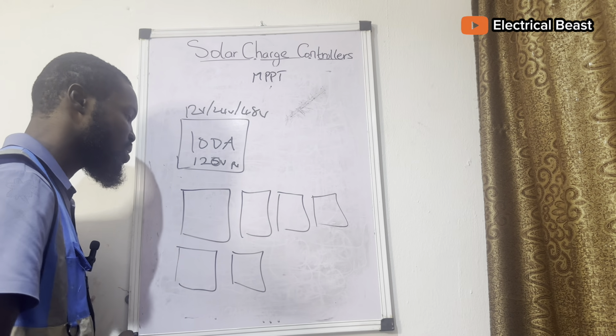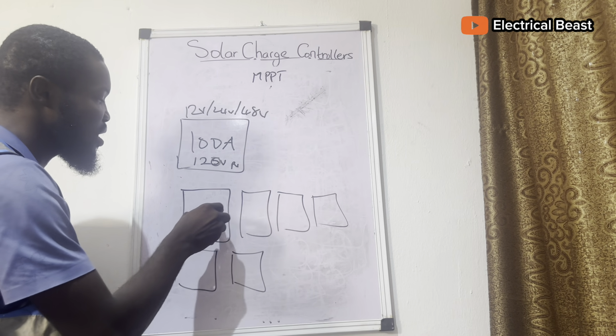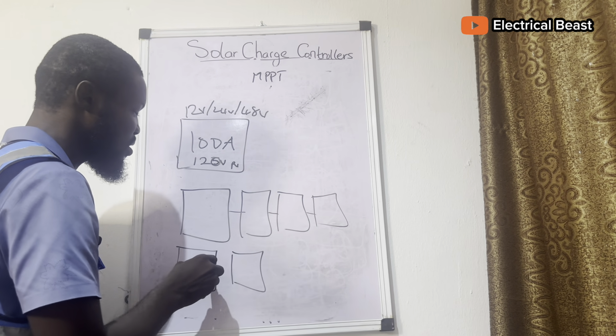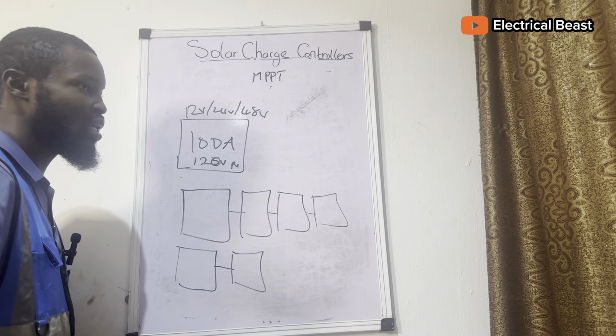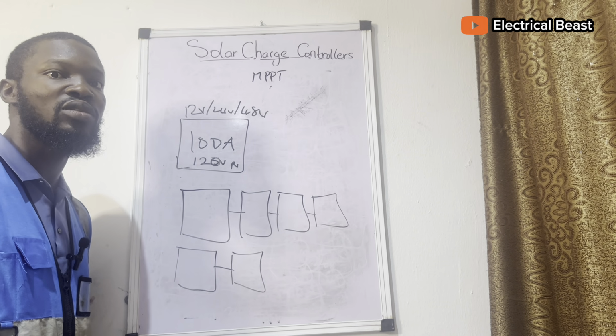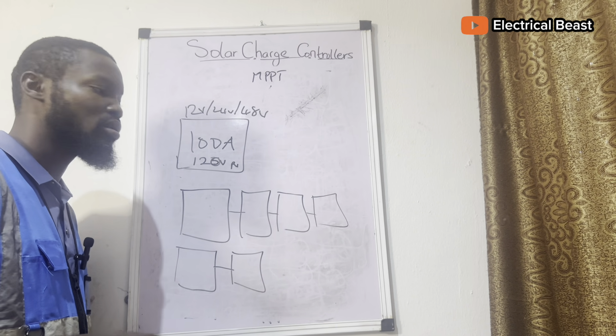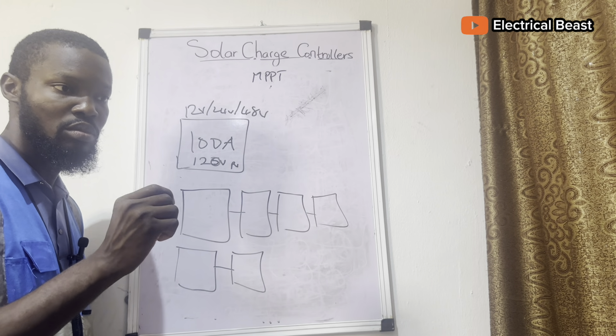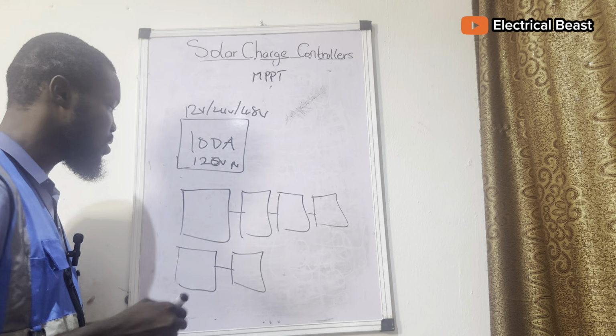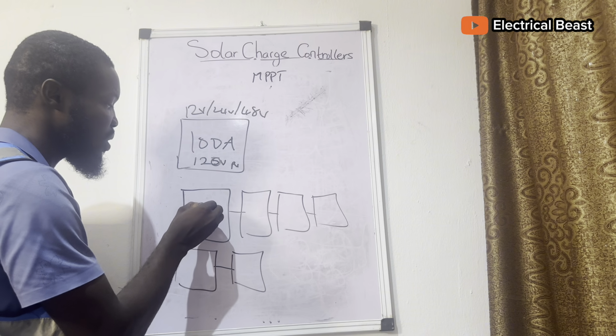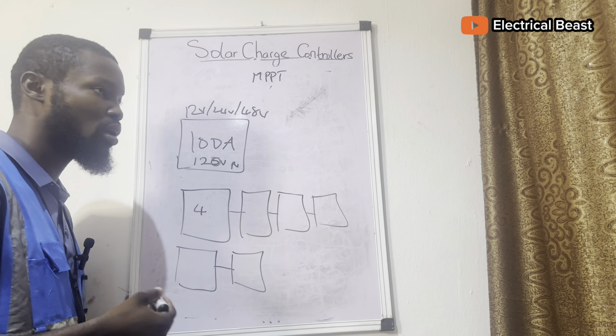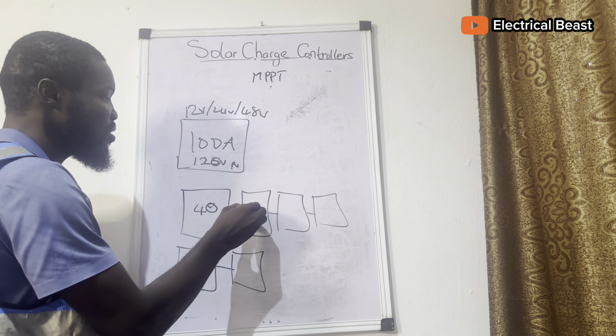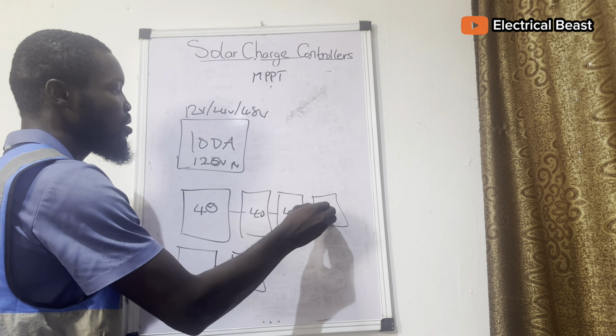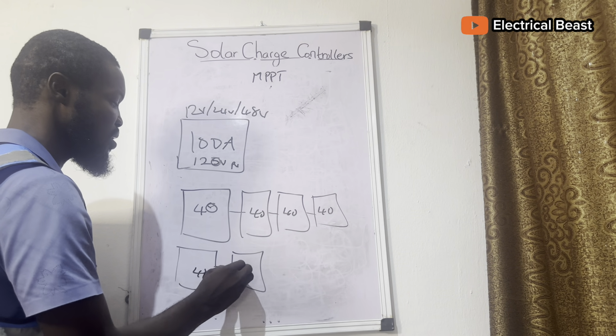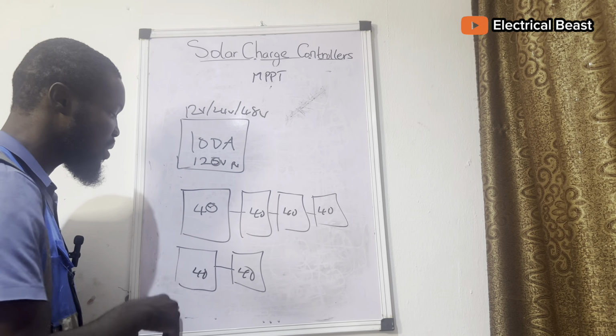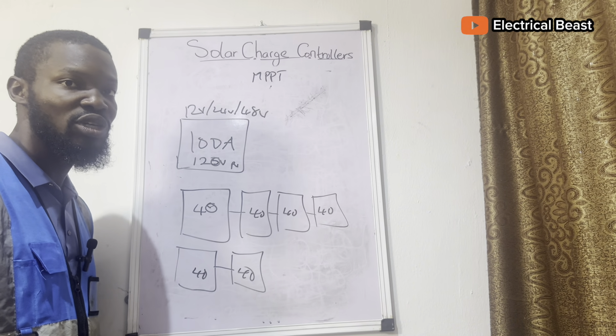If you have 6 solar panels, you are not expected to connect everything in series, because series connection increases the voltage and makes the current stay the same. The current doesn't change. So if this is a 48 volt panel, or let's say it's 40 volts, to make our calculation easy: this 40, this 40, this 40, this 40, this 40, and this 40. If you multiply 40 by 6, that's already 240 volts.